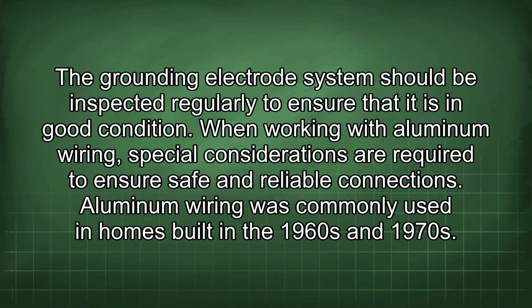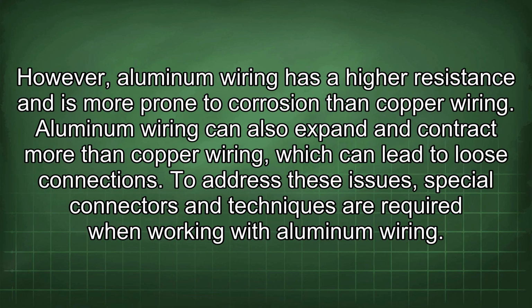When working with aluminum wiring, special considerations are required to ensure safe and reliable connections. Aluminum wiring was commonly used in homes built in the 1960s and 1970s. However, aluminum wiring has a higher resistance and is more prone to corrosion than copper wiring. Aluminum wiring can also expand and contract more than copper wiring, which can lead to loose connections. To address these issues, special connectors and techniques are required when working with aluminum wiring.